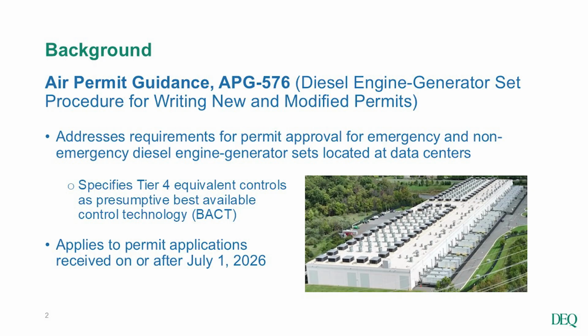Air Permit Guidance 576, or APG 576, establishes diesel engine generator set procedures for writing new and modified permits. DEQ updated this guidance in December of 2025 to address requirements for permit approval for emergency and non-emergency diesel engine generator sets located at data centers. It specifies Tier 4 equivalent controls as presumptive best available control technology, or BACT, which achieves the maximum degree of emission reduction considering energy, environmental, and economic impacts.